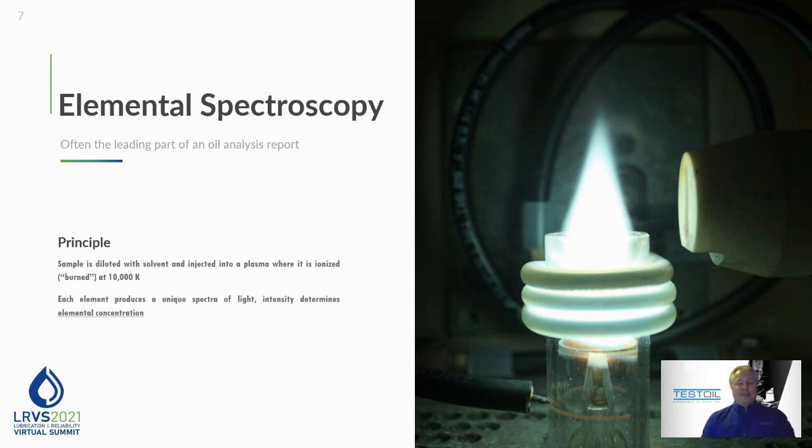What I mean by this is that if you had a sample, say some Babbitt bearing wear in your oil sample, this test wouldn't tell you had Babbitt. It would say you had lead and you had tin. Now, if you had a sample that had, say, a bronze or a brass piece to it, whether that be a gear or a wear plate or something like that, again, it wouldn't say that you had brass or bronze particles. It would say that you had lead and tin particles because that's one of the primary metals in brass and bronze is both lead and tin, but also copper.